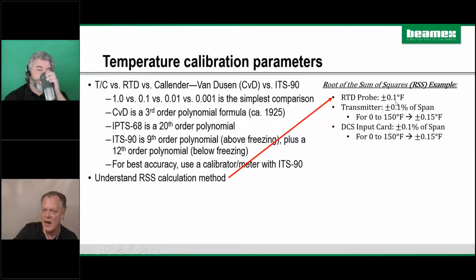I probably should have made it a little higher today. But the transmitter is 0.1% of span. So our span was 0 to 150, so we converted that to plus or minus 0.15. And then I'm saying the DCS input card is like the transmitter. So you have a tolerance for each item, and then we add them up? Well, some people do. If you're real conservative, you would say, if everything drifted in the same direction, to the fullest, I could still expect to get 0.4 degrees. That, to me, is punitive to do it that far.